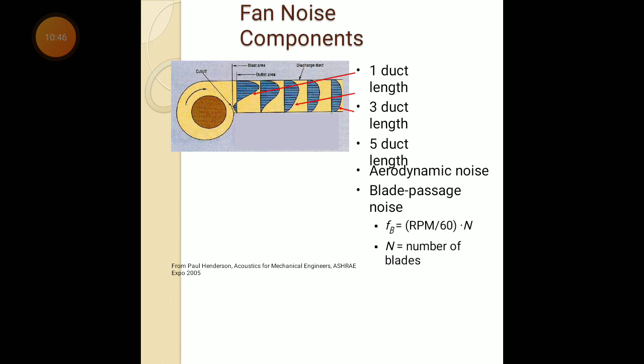And third one, blade passage noise. This blade passage noise is related to the interaction of the blade with respect to air, and it can be calculated as FB, blade passage frequency. FB is equal to RPM divided by 60 into N, where N is the number of blades and RPM is the revolutions per minute of the motor. So fan noise is shown in this picture.